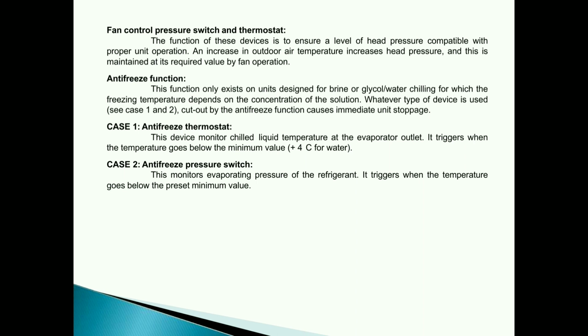Antifreeze function. This function only exists on units designed for brine or glycol water chilling, for which the freezing temperature depends on the concentration of the solution. Whatever type of device is used, see case 1 and 2, cut out by the antifreeze function causes immediate unit stoppage. Case 1, antifreeze thermostat.